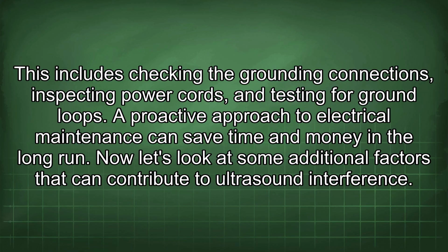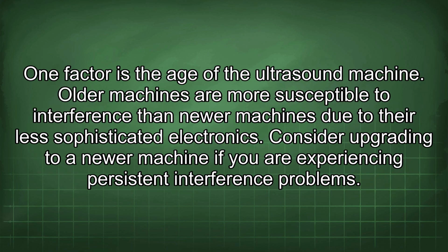Now let's look at some additional factors that can contribute to ultrasound interference. One factor is the age of the ultrasound machine. Older machines are more susceptible to interference than newer machines due to their less sophisticated electronics. Consider upgrading to a newer machine if you are experiencing persistent interference problems.